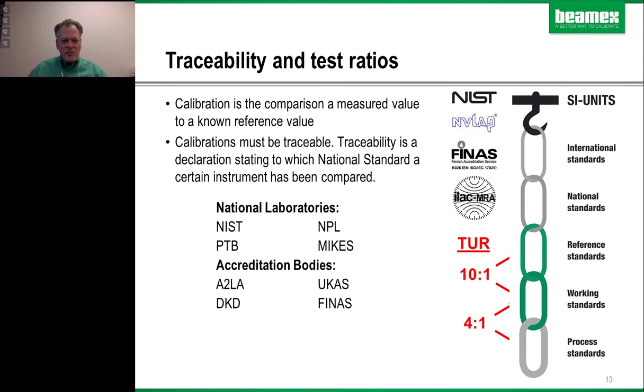All right, so getting into the basics, let's first talk about traceability and test ratios. You need to use quality equipment when you're performing calibration. And as Chuck said earlier, the base definition of calibration is comparing a measured value to a known reference value. So we're talking about the reference value part of this definition. When you're doing calibration, it has to be traceable. You need to have a pedigree showing that the calibrator is in good condition and is making the accurate measurements you need to run your plant. Traceability is typically, I almost call it a pedigree. It's some kind of document showing that a higher level reference standard was used to check that calibrator.